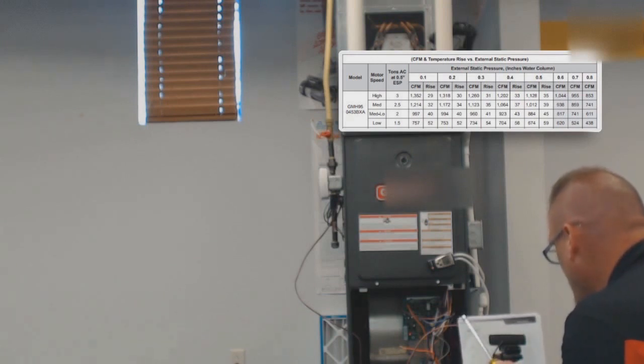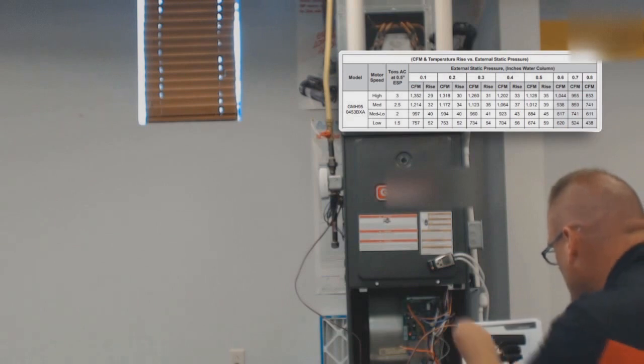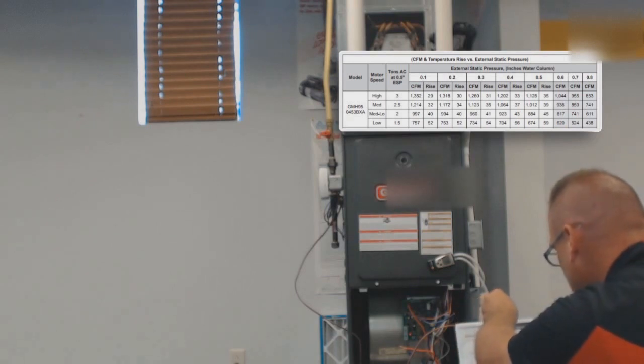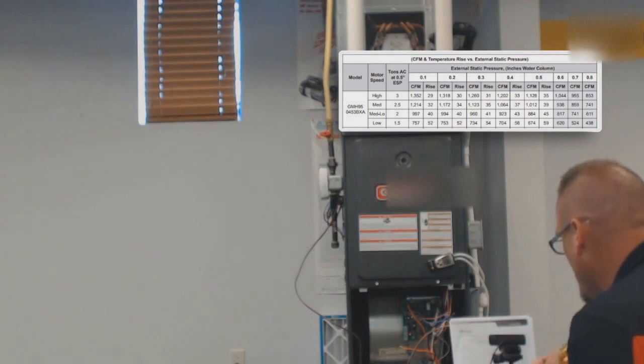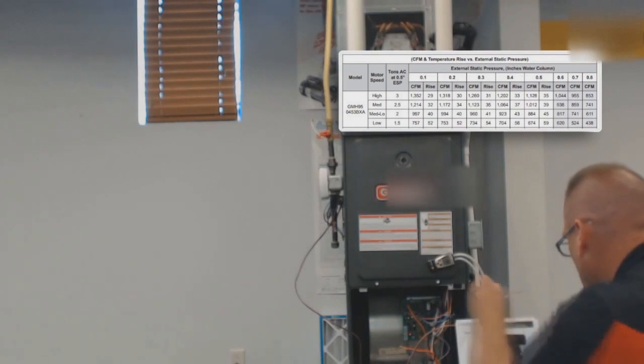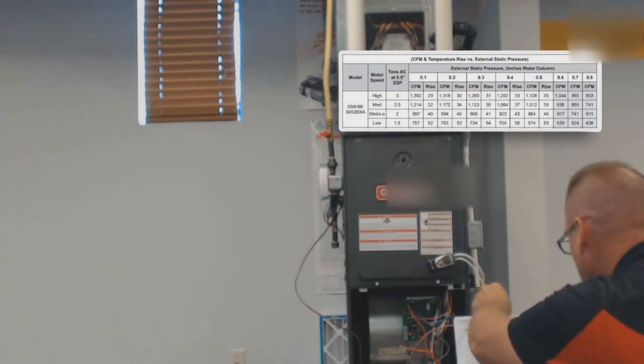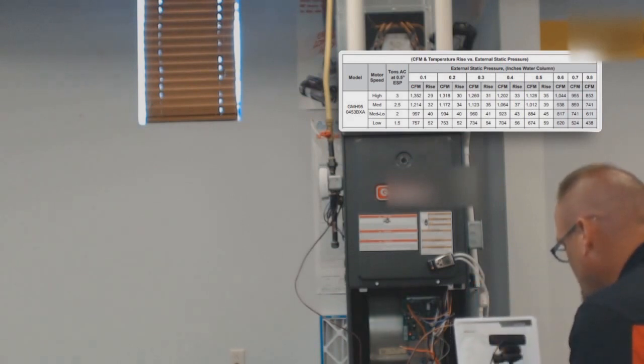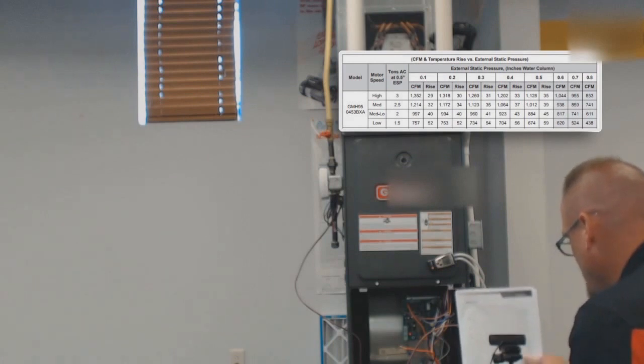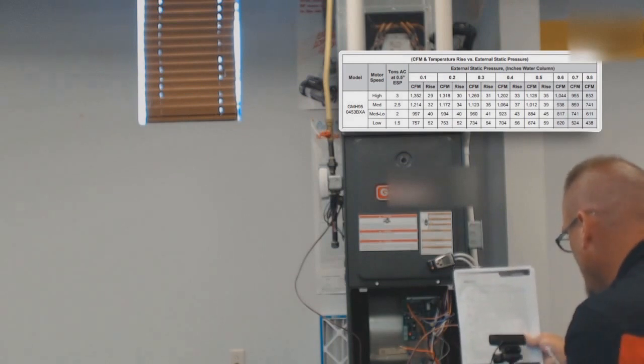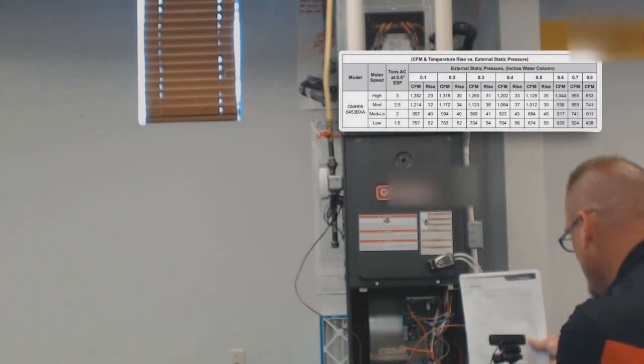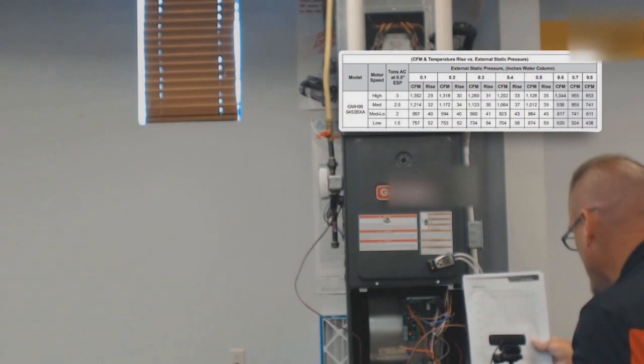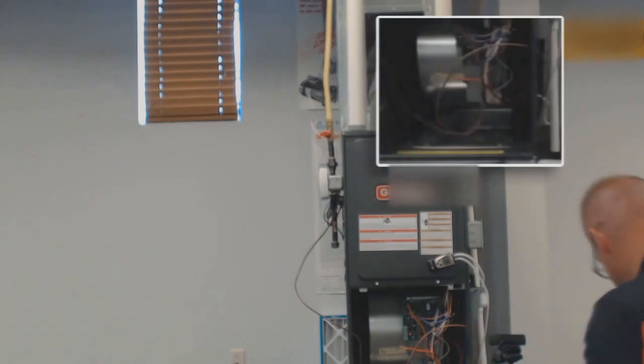We looked at the colors just a second ago, so that we were adept at looking inside of the bottom of this blower compartment and seeing those colors. Across the top here is your actual static measurement, and that static measurement is going to correspond to an airflow noticed right below, CFM. What we're trying to do is set this up properly for the manufacturer. Down at the bottom, it actually tells us, in order to be set up properly for this manufacturer, we want 400 CFM per ton for cooling for this setup. So we're going to try to find that.